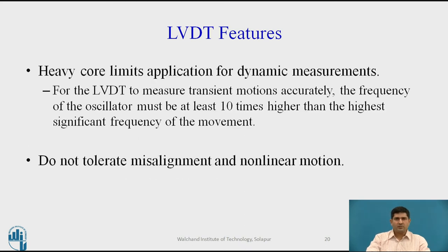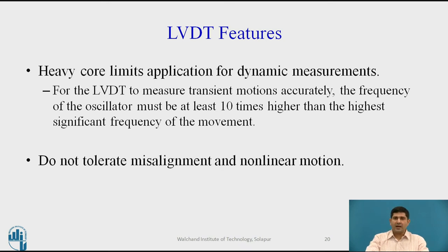Some of the negative features of LVDTs: the heavy core limits its application for dynamic measurement. For transient motions, the frequency of the oscillator must be at least ten times the highest significant frequency involved in the measurement. When it comes to misalignment and non-linear motion, textbooks typically mention that LVDTs are susceptible to misalignment and non-linear motion. However, I have seen manufacturers advertise their LVDT products as being tolerant to misalignment and highly linear — so I leave it to you to judge between what textbooks say and what manufacturers advertise.